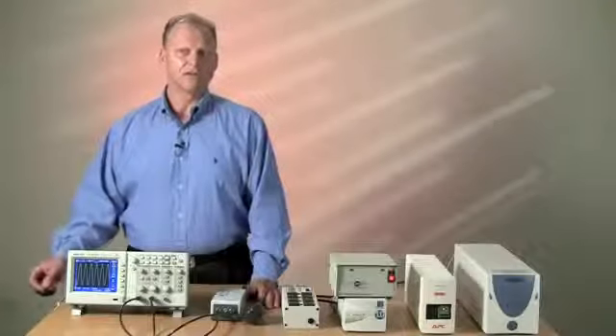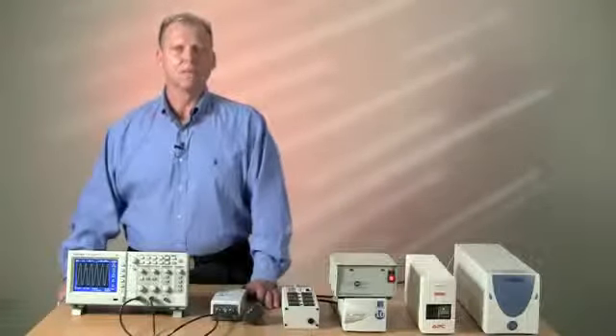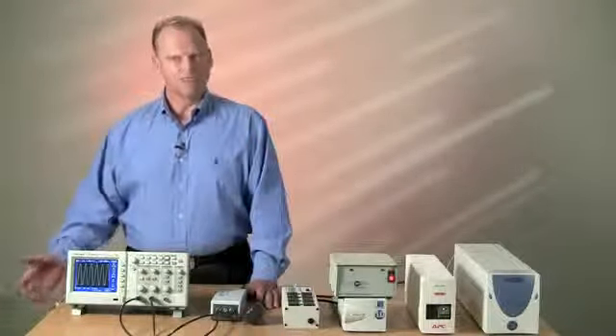The reason is that the microprocessor references ground in making its logic decisions, so if that transient or spike coincides with the clock pulse, the system locks up, does something stupid, maybe sends an order to the wrong terminal. But if you can keep those levels under 10 volts and under half a volt, you can really attain system reliability.